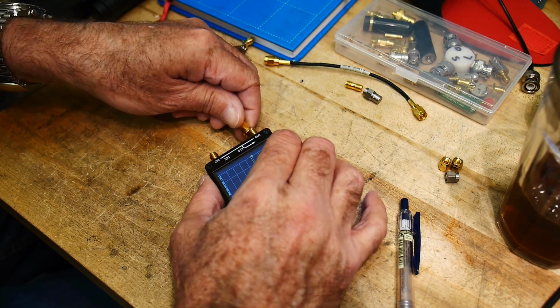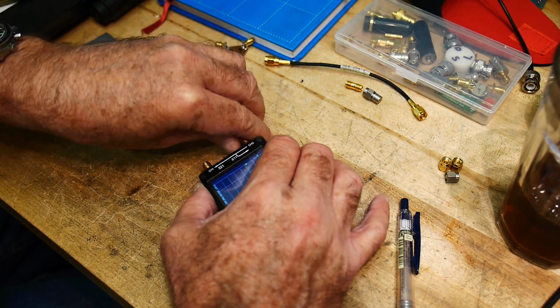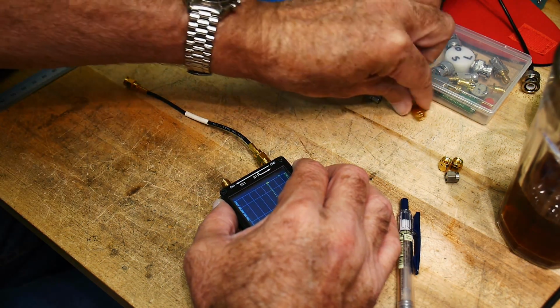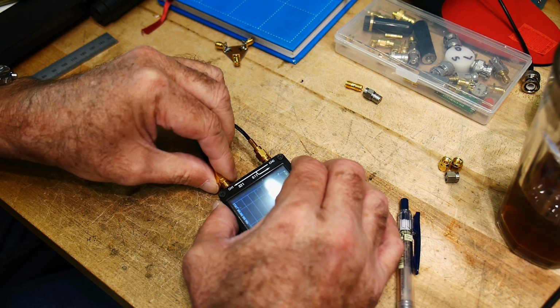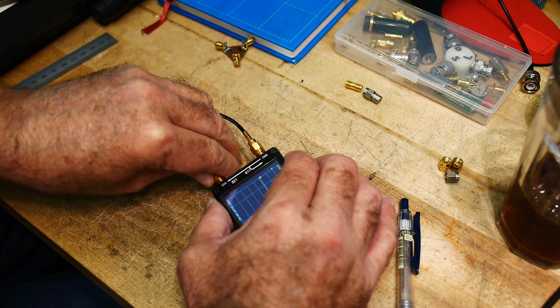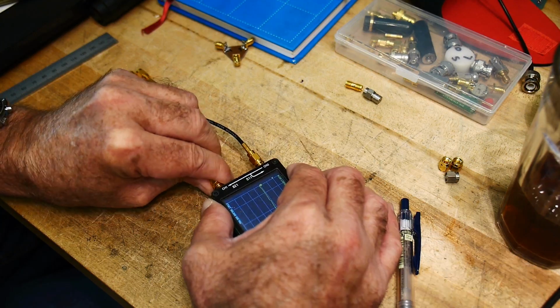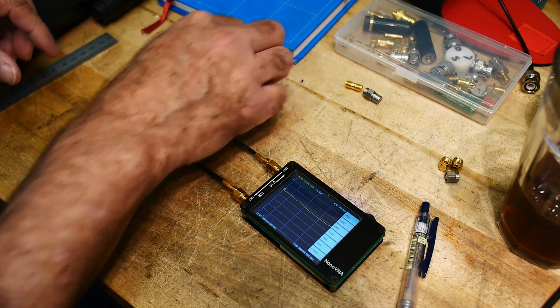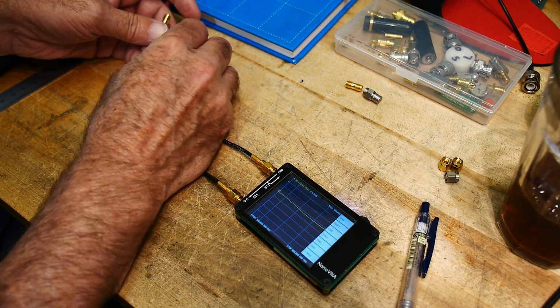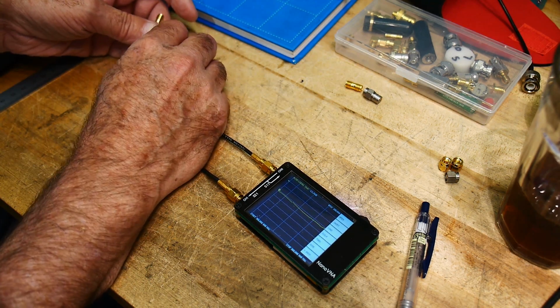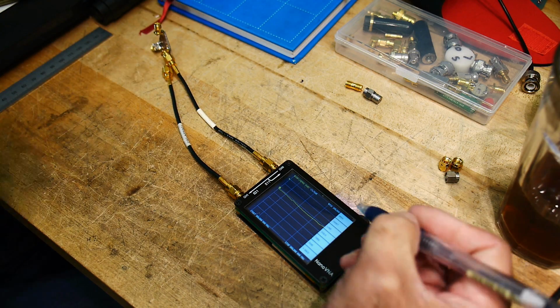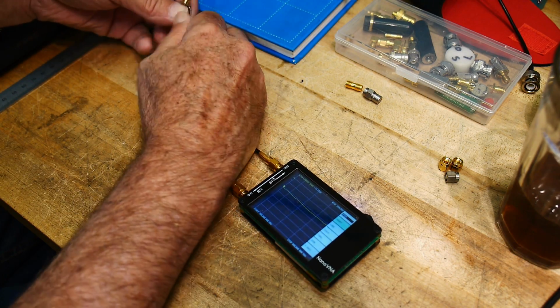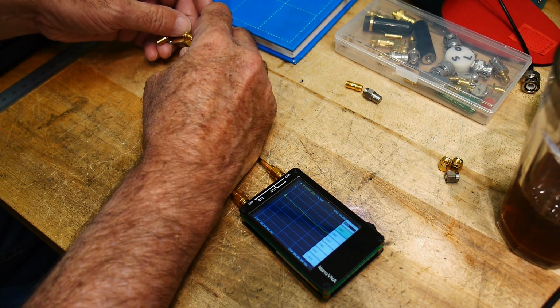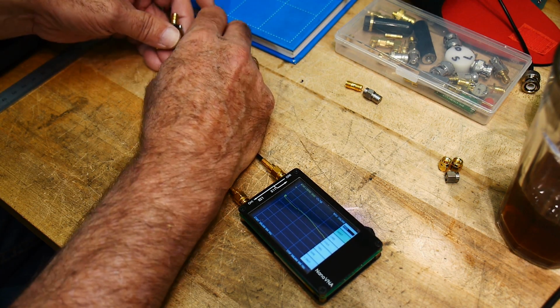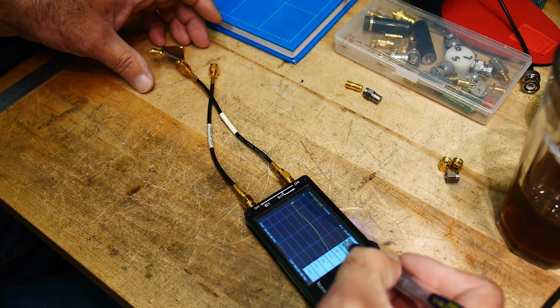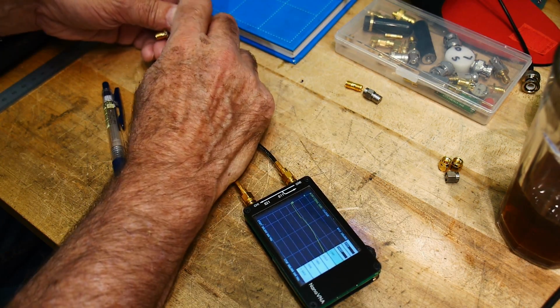Okay, so we're going to be making measurements on the end of some short pieces of coax here. So we're going to calibrate at the end of those. So we're going to try to be as accurate as we can. So we have these on there. All right. So we're going to put an open on S11. And now we'll do a short. We'll do a load.